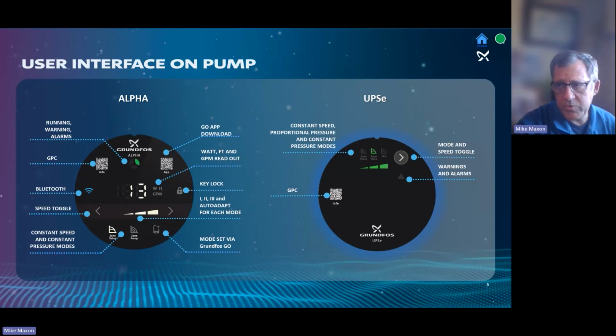The Bluetooth connection. I know it looks like Wi-Fi, but it's actually Bluetooth. The arrows here will toggle you through the different settings of the pump, different speeds. But if you touch this icon here, it'll put it in constant pressure. Touch this one, it'll put it in constant curve, and then you can change the speed. And over here would be auto adapt, just like the old one was in that way. If the product has been set up by the phone, the phone icon will be on. So that lets you know that none of these settings on the screen are being used. It is set up through the phone.